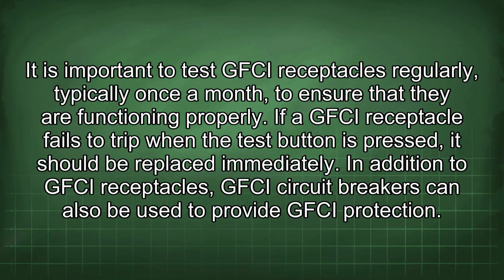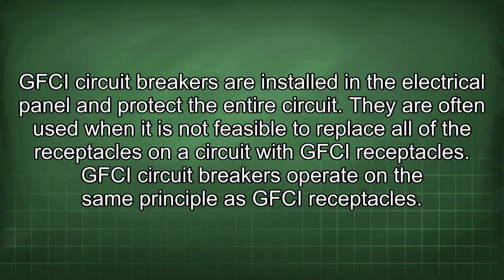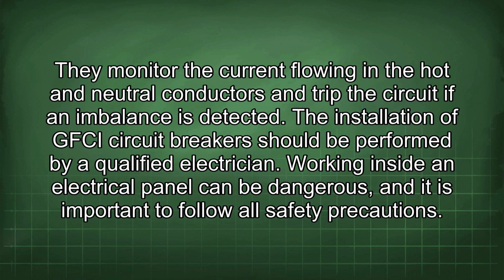In addition to GFCI receptacles, GFCI circuit breakers can also be used to provide GFCI protection. GFCI circuit breakers are installed in the electrical panel and protect the entire circuit. They are often used when it is not feasible to replace all of the receptacles on a circuit with GFCI receptacles. GFCI circuit breakers operate on the same principle as GFCI receptacles. They monitor the current flowing in the hot and neutral conductors and trip the circuit if an imbalance is detected. The installation of GFCI circuit breakers should be performed by a qualified electrician. Working inside an electrical panel can be dangerous, and it is important to follow all safety precautions.